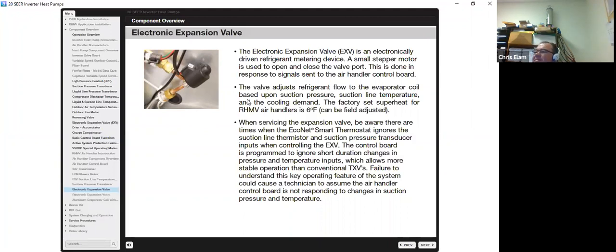Basically, the EEV is an electronically driven refrigerant metering device. A small stepper motor is used to open and close the port. This is done in response to signals that are sent to the air handler control board. The valve adjusts refrigerant flow to the evaporator coil based upon suction pressure, suction line temperature, and the cooling demand. Factory set is approximately 6 degrees superheat.